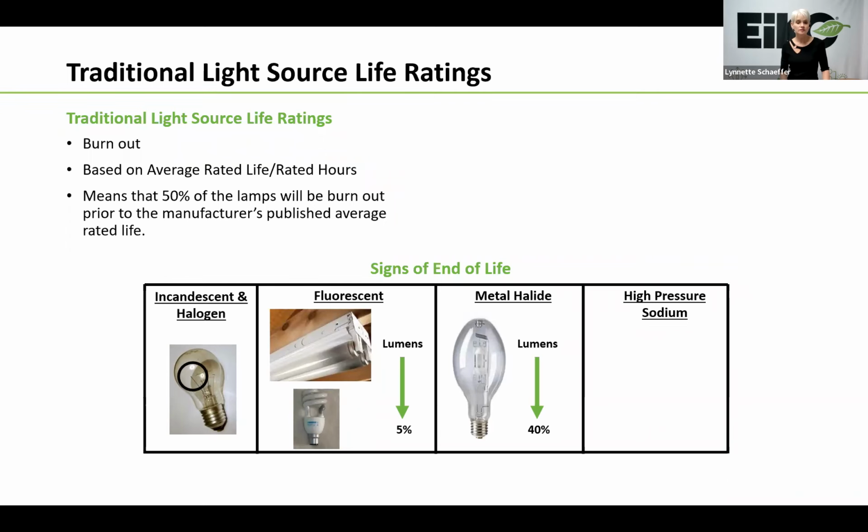Metal halide end of life is caused by sodium loss from the arc tube. What will happen is the lamp will have a harder time starting, and it may also start giving off a blue or kind of pink color. The other thing about metal halides is it will have a noticeably lower lumen output from day one, about 40% as a matter of fact. Now, high pressure sodiums will do something that I referred to earlier. It's called cycling. When they get close to going out, one day the lamp will be turned on, and the next day it will be out.